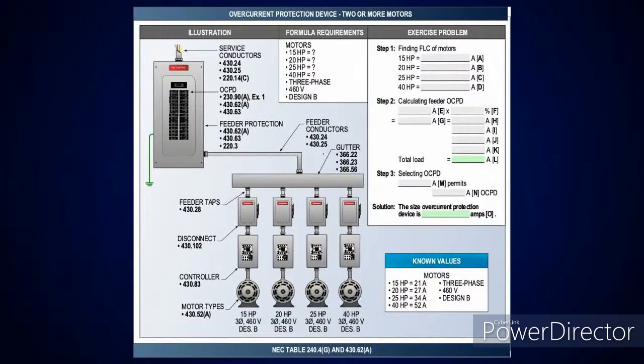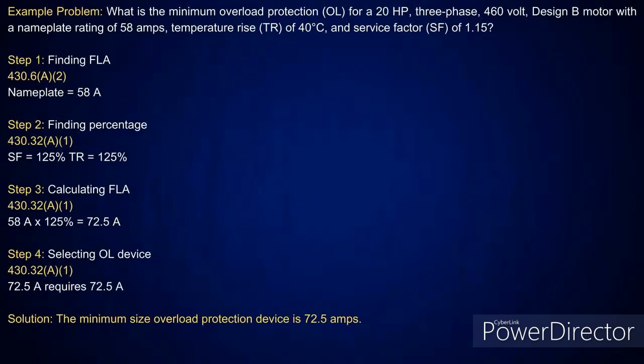And then here you've got different motors. They're 460 volt, 3-phase, Design B motors. We're sizing an inverse time circuit breaker, and you have a 15, 20, 25, and 40 horsepower for your exercise problem. And then do this overload protection to them. Then we'll call it quits on this one.